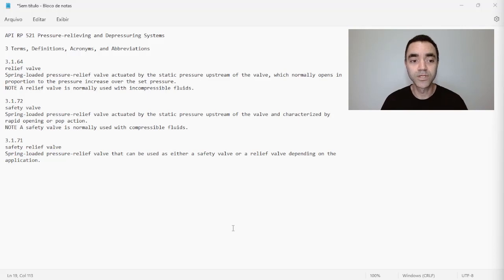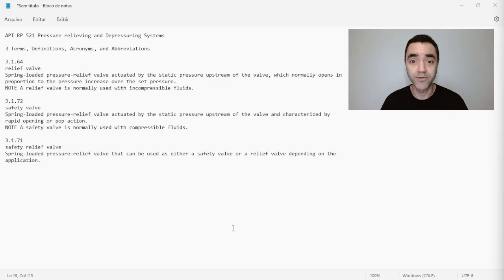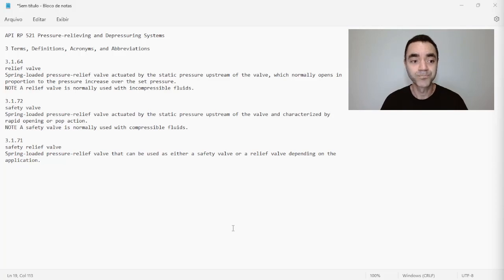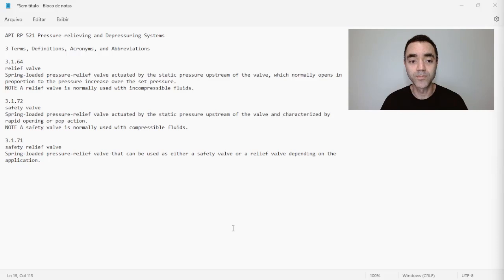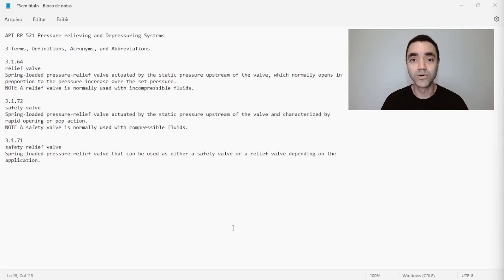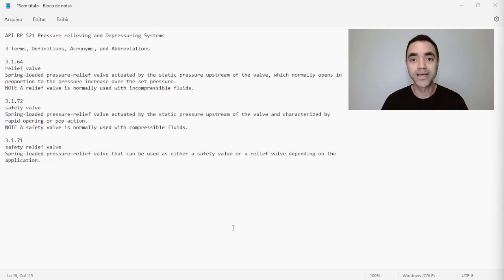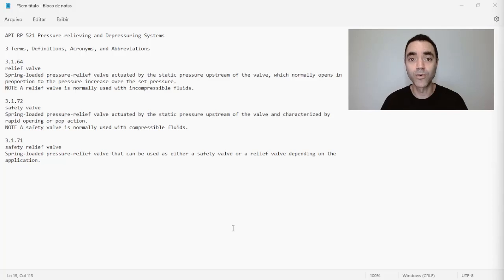So the relief valve, according to the API, is a spring-loaded pressure relief valve actuated by the static pressure upstream of the valve, which normally opens in proportion to the pressure increase over the set pressure. And there is a note: a relief valve is normally used with incompressible fluids.